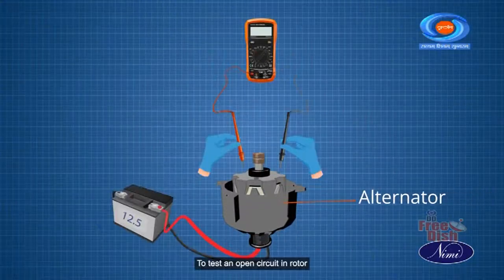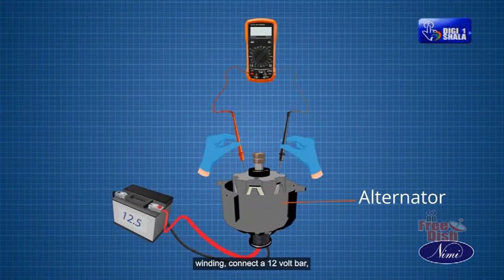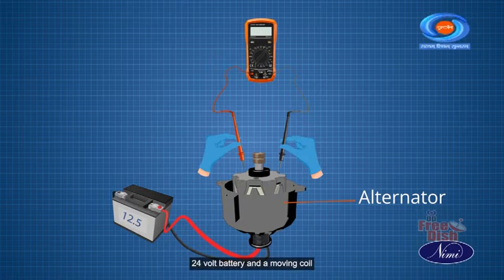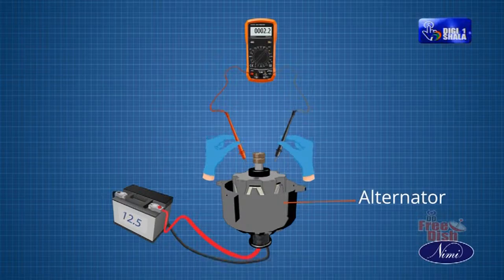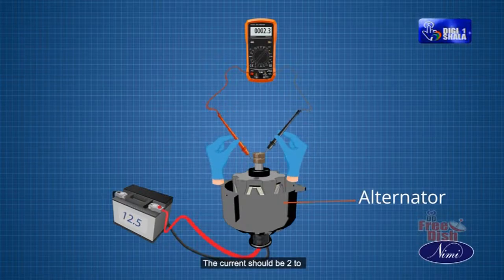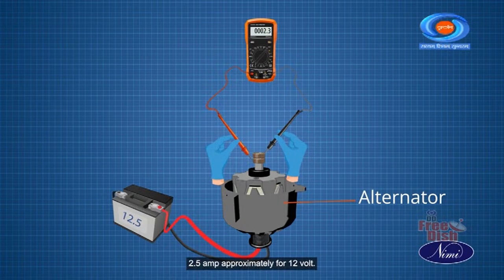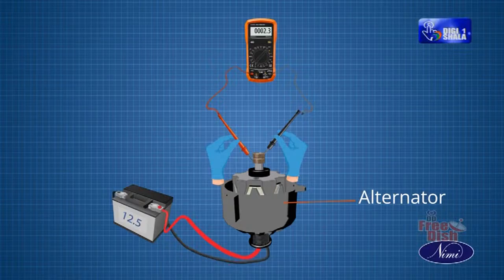To test an open circuit in rotor winding, connect a 12 volt or 24 volt battery and a moving coil ammeter between the slip rings. The current should be 2 to 2.5 amp approximately for 12 volt. If not, renew the rotor.